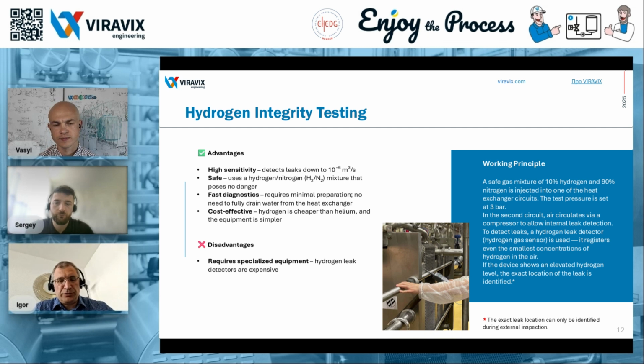Well, the fact that we use a hydrogen-nitrogen mixture is both an advantage and a drawback. The drawback is that the hydrogen concentration in the final mixture is reduced, from 100% down to 5 or 10%. Accordingly, the detection sensitivity also decreases, since we're detecting hydrogen specifically, not the mixture as a whole. But the advantage is that nitrogen has a much higher solubility in water. This means there's no need to drain the heat exchanger before performing the hydrogen-nitrogen test.